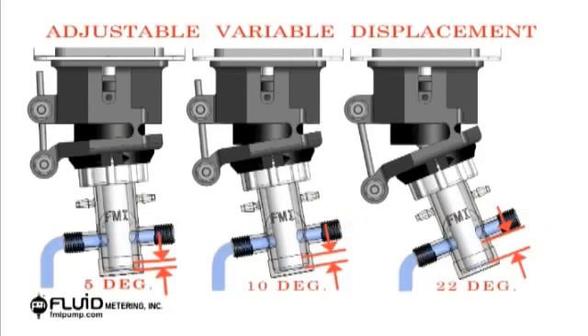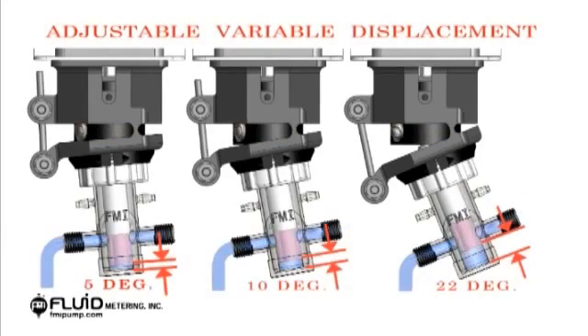This design gives the customer the best performance for their application by eliminating valves, utilizing ruby hard ceramic components to maximize life, and eliminating dead space inside the pumping mechanism to maximize bubble clearing and deliver the most repeatable fluid control product with a coefficient of variance of less than 0.5 percent.